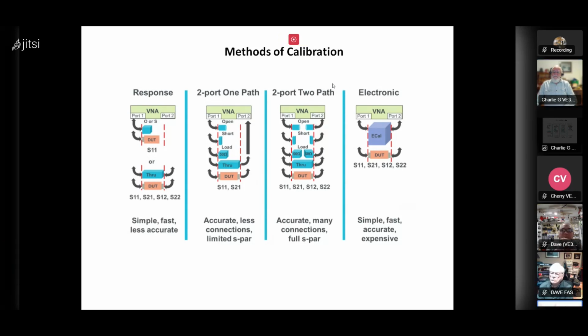I have the H4, and one of the things they talk about is the isolation calibration, and I've never really been clear what that's about. That is basically the through measurement with nothing in here, just an open circuit between here. Okay, thanks.